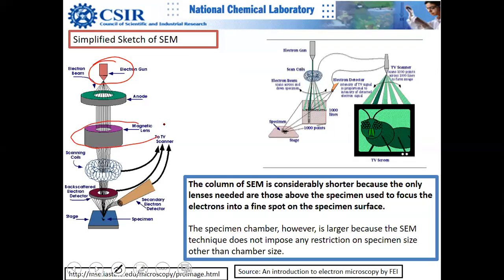You have a set of lenses, and the main scanning coils are a special magnetic lens responsible for moving the beam in X and Y directions. These scanning coils are specifically designed to scan the electron beam over the specimen surface.